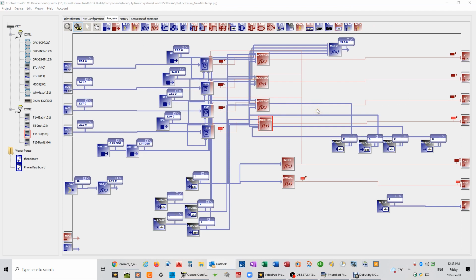So now let's review something I mentioned earlier about dew point control. This system is hot water or conditioned water going through the ceilings. And in the summertime, I am going to be flowing chilled water through the ceilings to allow the rooms to cool down. So chilled water will go through a ceiling. It will allow the heat in that room to be absorbed by the chilled water and extracted from the room, lowering the temperature in the room, providing cooling in the room. But what's important is that the temperature of the ceiling is never below the dew point of the interior air. And that's where those dew point sensors came into place.